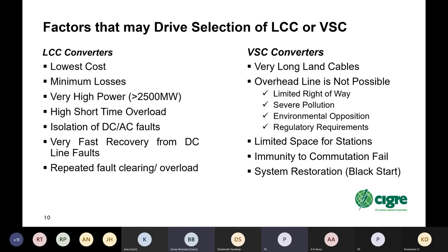LCC converters have minimum losses. In terms of looking at the losses, numbers that are usually given are for an LCC converter at full load, the losses may be in the order of about 0.7% of the transmitted power at each converter station. So 1.5% losses on both converter stations at the two ends, whereas with VSC, the losses may be in the order of 1% at full power. And then you're looking at, for both stations, losses in the converters of about 2%. So that's quite a significant difference when you have a very high power link. LCCs are much more suitable for very high power links, for instance, greater than 2,500 megawatts.